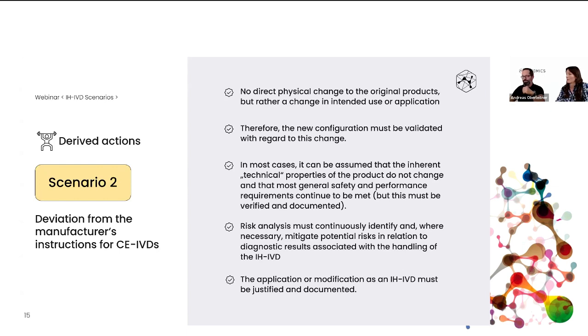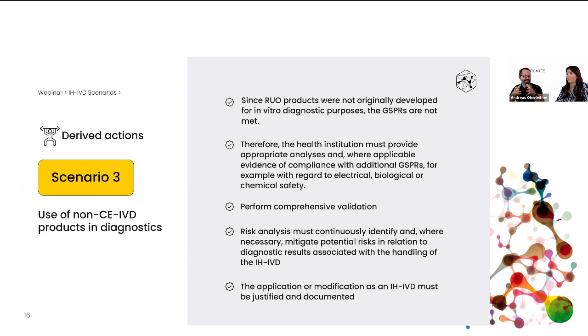Of course, it still depends, because even RUO devices like instruments would be tested according to some suitable standards in this area, because it's an electrical device. And they might even bear a CE mark. Here you need to be careful. The CE mark does not always mean it's a CE-IVD. There are also other regulations and directives which can lead to a CE mark. For example, for instruments, you still have an EMC directive or a low voltage directive, etc. These devices bear a CE mark, but that does not necessarily mean it's an IVD.